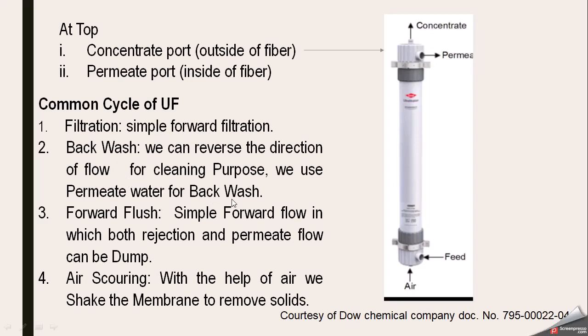The second operation mode is backwash. We can reverse the direction of flow for cleaning purposes — water now comes from inside and goes outside, cleaning the membrane. This is called backwash cleaning, and we use permeate water for backwash.